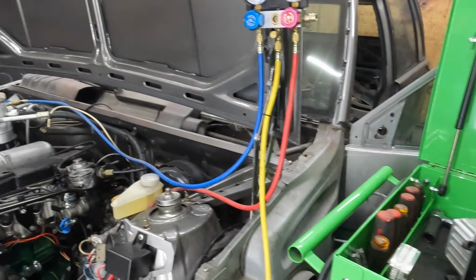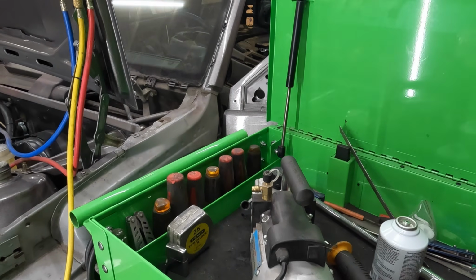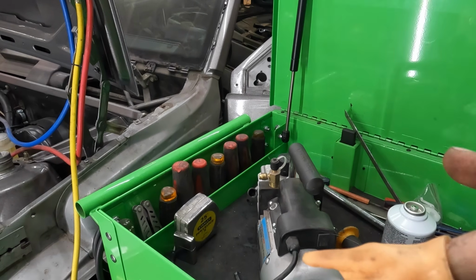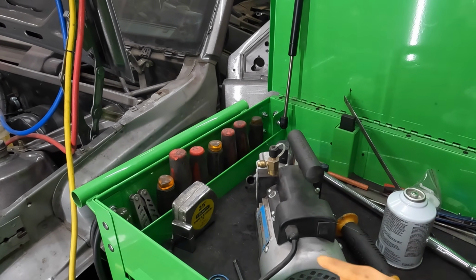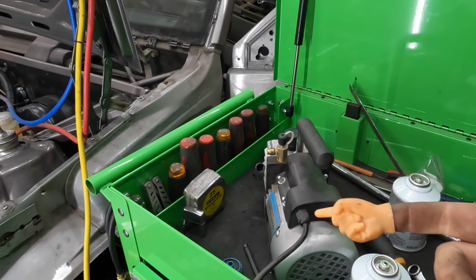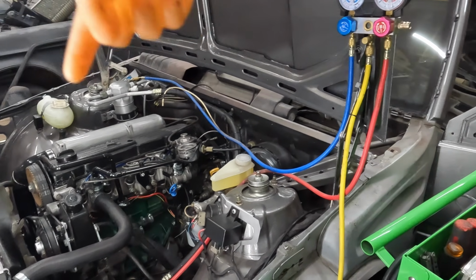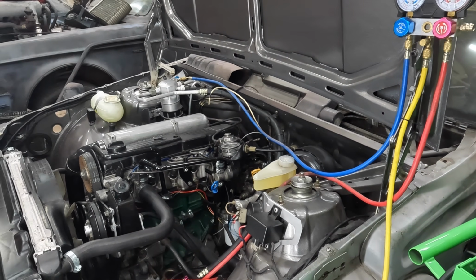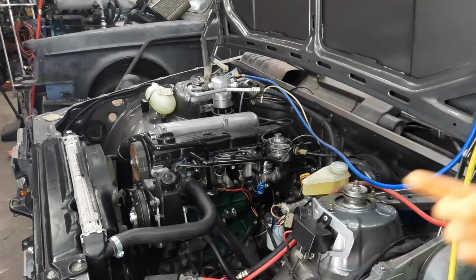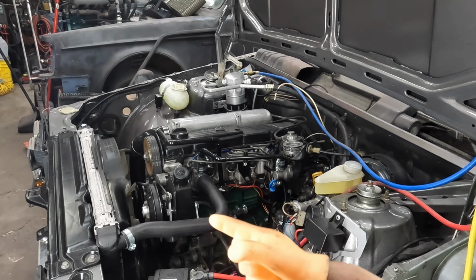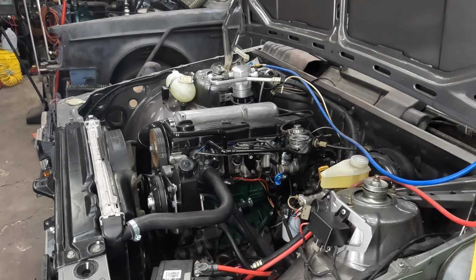I'm not sure if I mentioned it, but when doing a leak check with the vacuum pump, it is possible to have a false positive result. That's because if something somewhere is somehow acting as a check valve, it could be holding that vacuum by not letting air in, but once you charge the system with pressure, it could let refrigerant out.